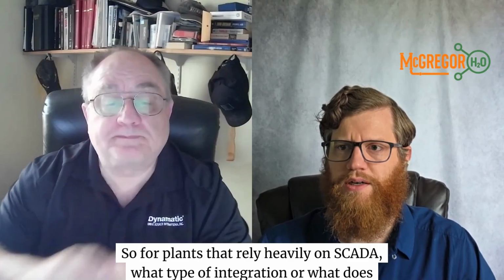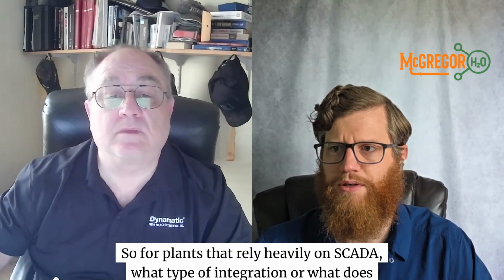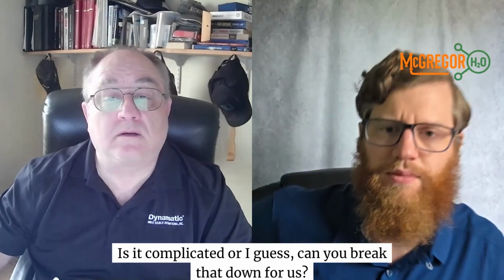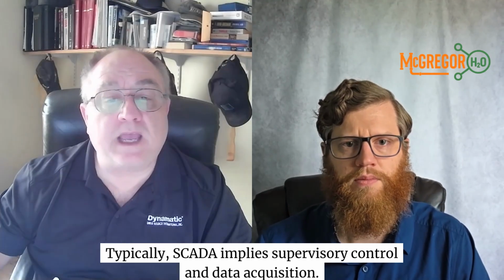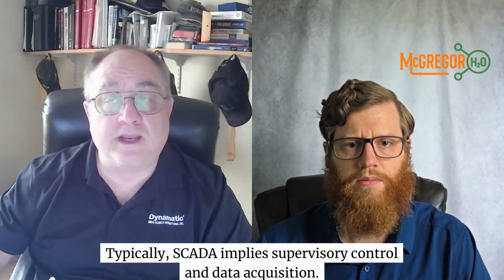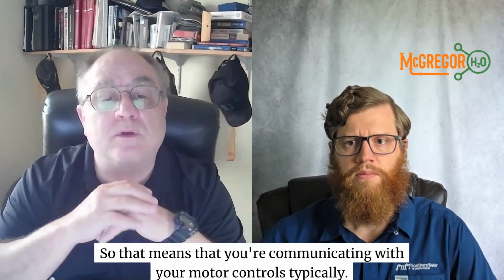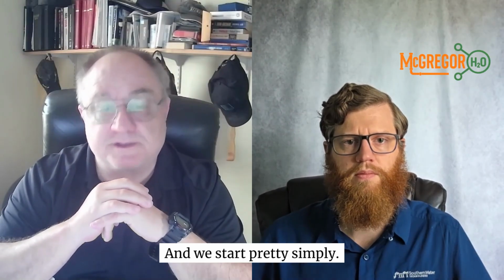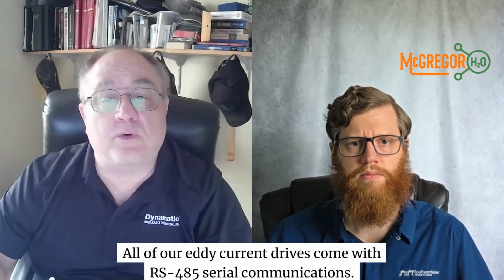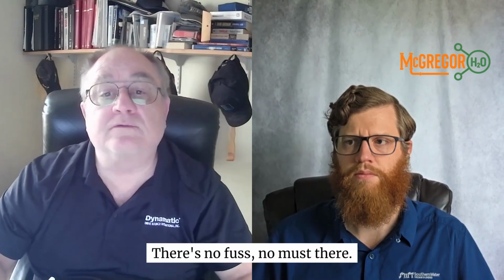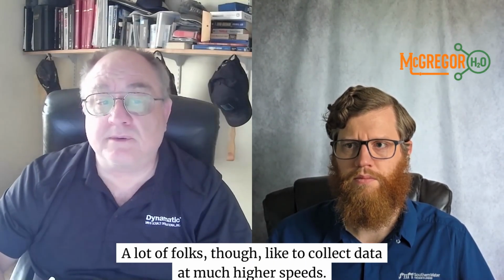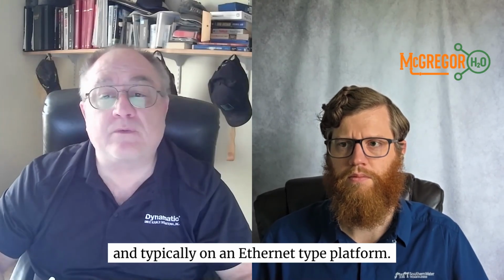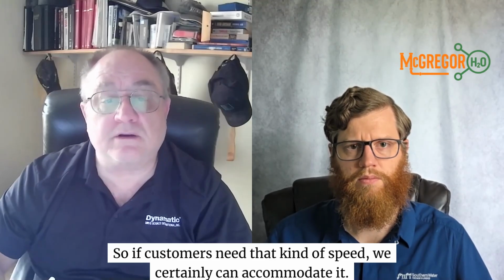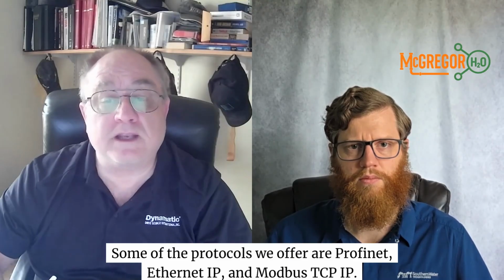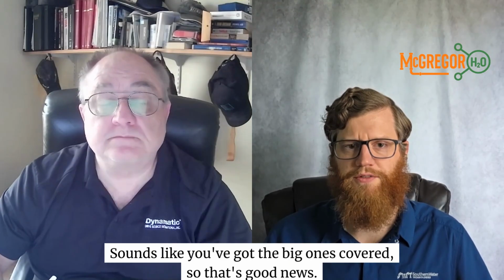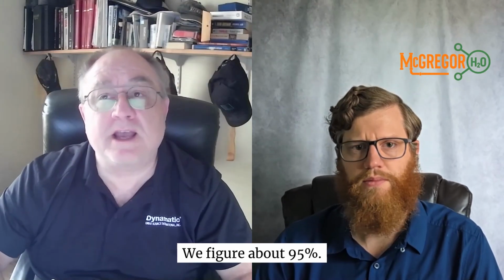Correct. So for plants that rely heavily on SCADA, what does integration look like? Is it complicated? Can you break that down for us? Sure. Typically, SCADA implies supervisory control and data acquisition. So that means that you're communicating with your motor controls typically. And we start pretty simply. All of our eddy current drives come with RS-485 serial communications, pretty standard. There's no fuss, no muss there. A lot of folks, though, like to collect data at much higher speeds and typically on an Ethernet type platform. So if customers need that kind of speed, we certainly can accommodate it. Some of the protocols we offer are Profinet, Ethernet IP, and Modbus TCP IP. Sounds like you've got the big ones covered, so that's good news. We figure about 95%. Oh, absolutely.